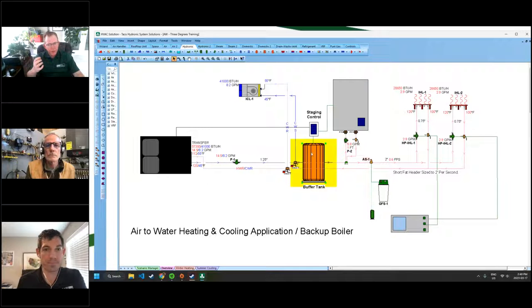The other thing that I like about it is I have the ability to charge this. So if you're in time of use, especially if you're in Ontario, because there's a lot of rumors of our electrical rates dropping significantly, well, I want to make sure that when I have a really low cost of utility, I charge this tank as hot as I can get it without hurting the heat pump, and then the boiler comes on.